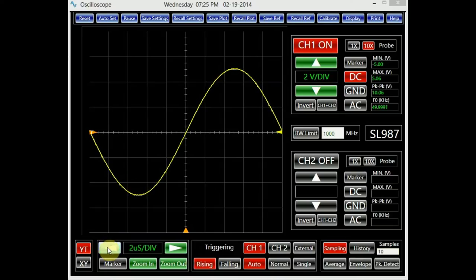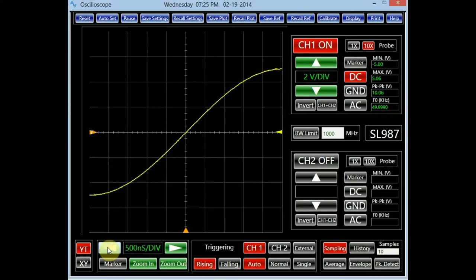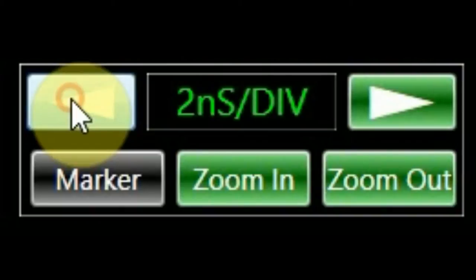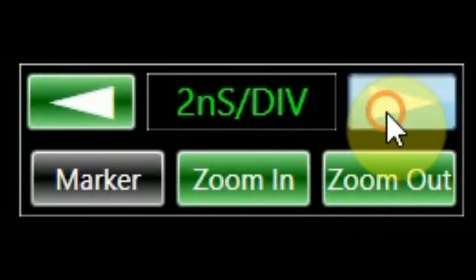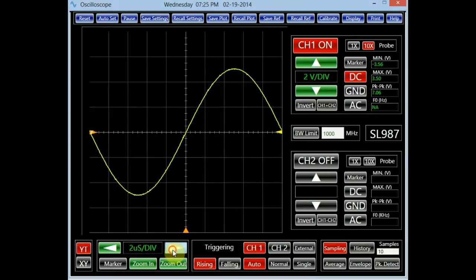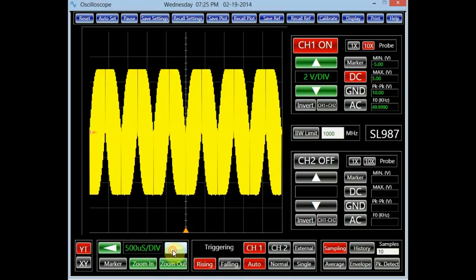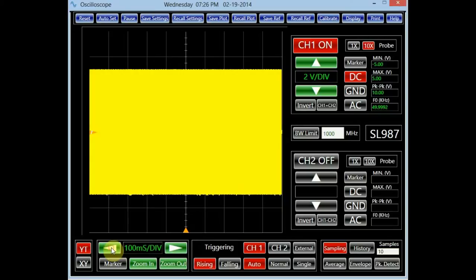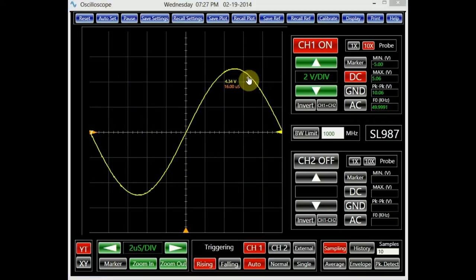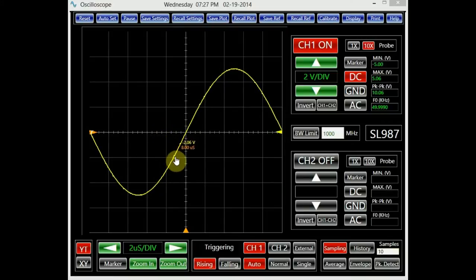The button with the left-pointing arrow in the timing panel reduces time per division, and the button with the right-pointing arrow increases it. The range of the timing scale adjustment is from 1 ns per division to 100 ms per division. In order to view a full cycle of the signal on channel 1, we need to adjust the timing scale to 2 microseconds per division. Notice that the data corresponding to the position of the mouse is also displayed near its position in each channel's corresponding color.